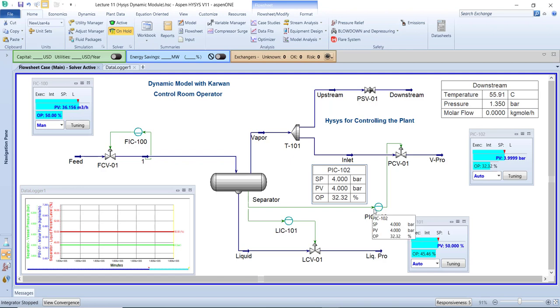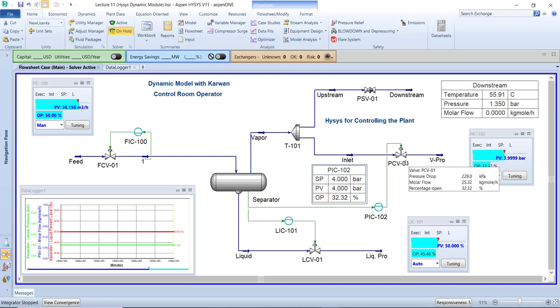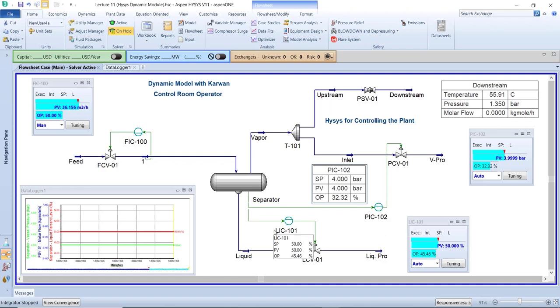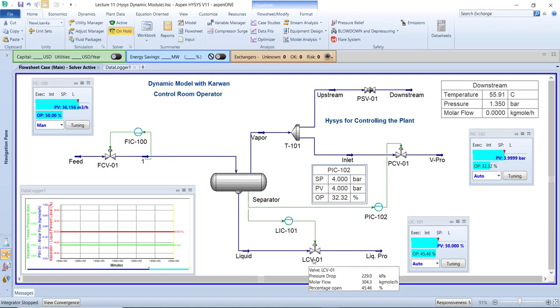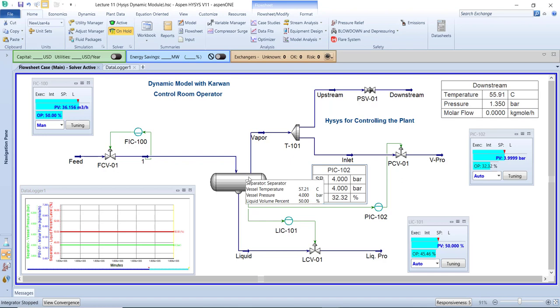In the controller, we set the set point (SP) of the separator to four bar. The process variable (PV) equals four bar — the same — and the output of the PCV control valve is 32%. This means we can control and set the pressure of the separator from the control room through the controller that the control operator monitors all the time. We also control the separator level using the LIC controller in the control room, and the LCV in the field. The separator level is normally maintained at 50%.